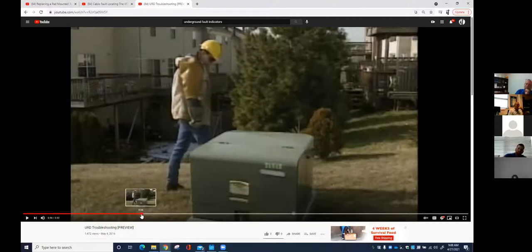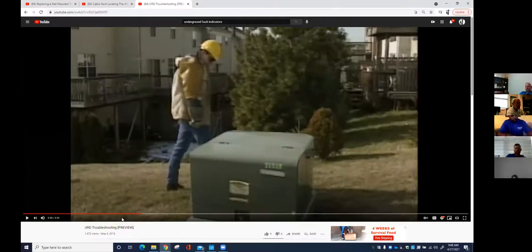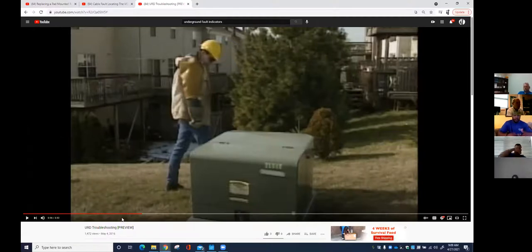When we saw that blown fuse and you're the first guys out there, we typically went to every piece of underground equipment and did a visual inspection inside also. This guy just does a walk around. Do remember, if you're going to be in a subdivision, you might have 20 or 30 transformers in a string. If you go through and look at every single one, that's a quick inspection because most of your failures as far as the cable is concerned are at the connection points — that includes the elbow and where it goes into the transformer. But I just want to add: this guy just does a walk around. We did an inside inspection also.